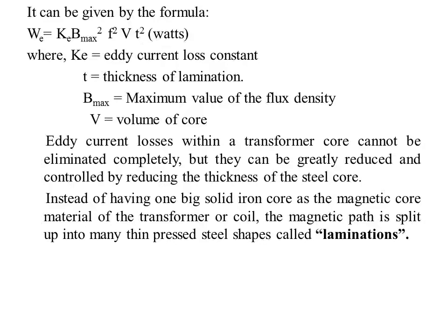The one thing we need to remember is that iron loss or core loss is a constant loss, because it depends mainly on the volume of the core, thickness of the core, and magnetic flux density. All these parameters can be kept constant. It also depends on the input voltage, which is also maintained constant while the transformer is working. So the core loss or iron loss is constant.